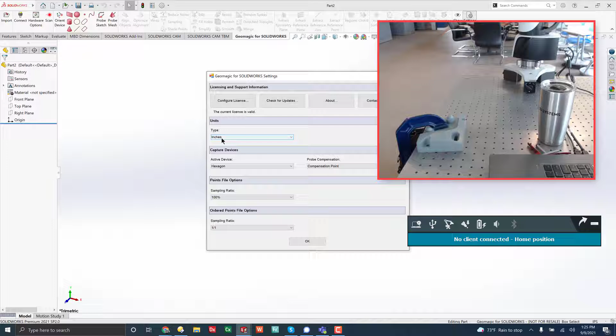You also have the ability to change the compensation point, whether you use the first point vector of the probe to offset your probed information or the last point compensation click. But most of the time people are using the last point compensation. And then you can set your units here as well. So if I hit OK, you hit connect. If I disconnect real quick, you'll see that it grays out the scanning tools, and if I hit connect, it will open those up.